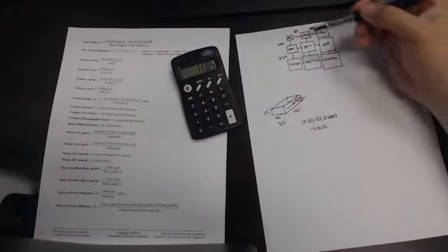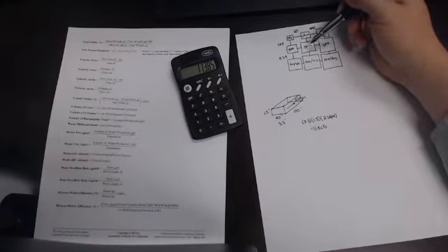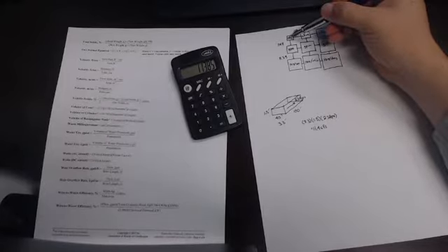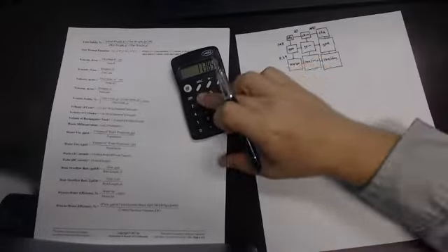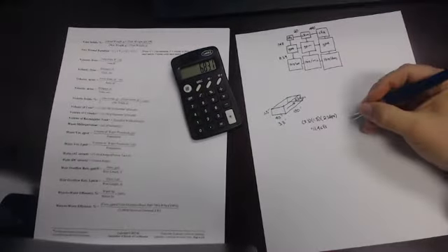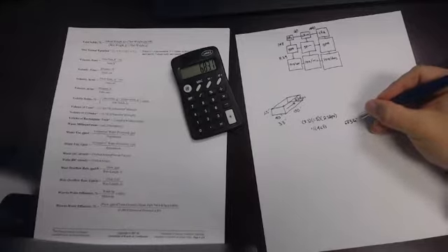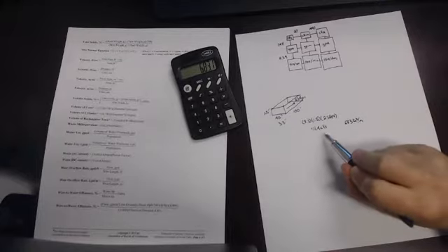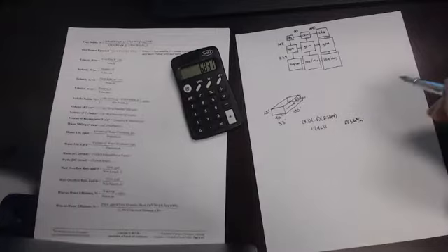So if you take this and then look at our little chart, we're at cubic foot per second. So if we want to get to gallons per minute, say you have a chemical pump or something that's pumping, you don't know how fast it's pumping. All you would do is multiply that number by 60 and then multiply it by 7.48. So when you multiply that number times 60, you get 683 cubic foot per minute. So that same 11.4 cubic foot per second, if you let it go for a full minute, you'll pump the 683 cubic foot per minute.